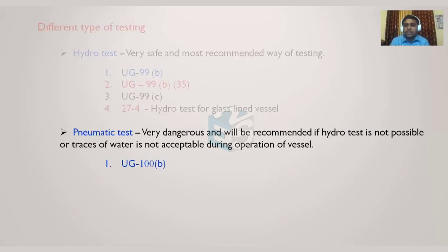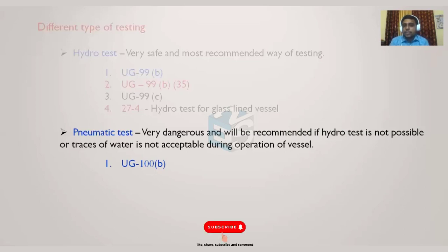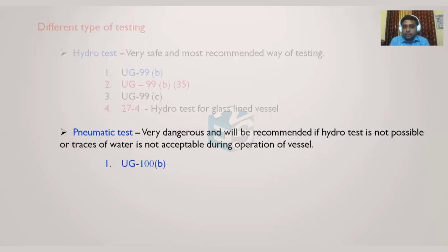In pneumatic testing, the weight of the gas is essentially negligible — just a few milligrams, grams, or kilograms. In hydro testing, the entire volume is filled with water, adding significant weight. If the support system cannot handle that load, hydro testing is not preferred. The pressure for pneumatic testing is given in UG-100D and UG-100B, including endnote 35, which will be covered in upcoming slides.